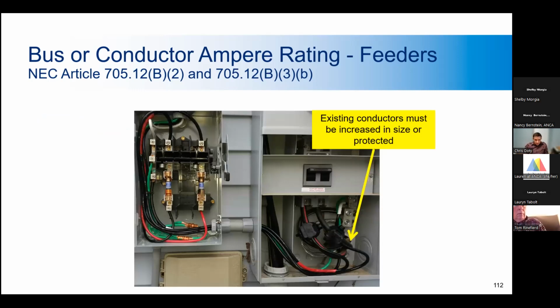And here we have an example of this. We see the interconnection on the load side of the 200 amp breaker on an apartment where the apartment panel didn't have a main breaker. And you have a meter pan, which is basically this, with an integral disconnect. The existing conductors and possibly the bus bar downstream can be strained by this additional current. So potential solutions include conductors and bus bar increased in size for the new additional current, or additional protection by adding an overcurrent device before the loads, such as a main breaker in the panel.